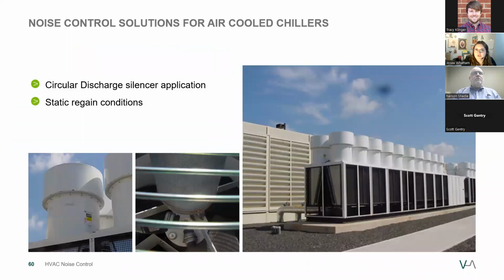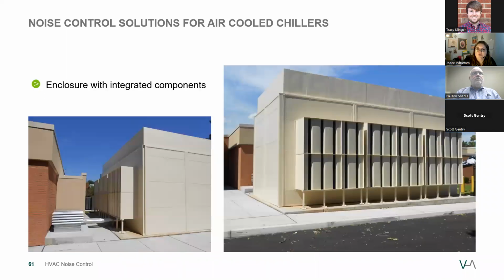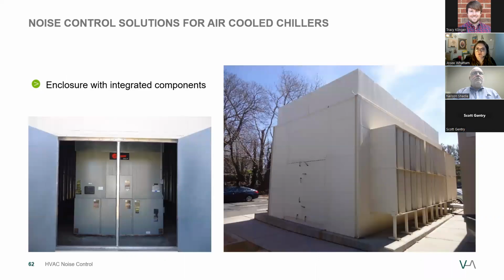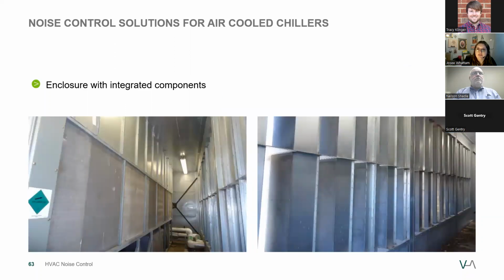This is another configuration, which includes circular discharge silencers. The center bullet of the silencer lines up with the fan hub diameter for static regain conditions. And another solution here is an enclosure with integral intake and discharge silencers. These photos are showing the end wall with double access doors. And the inside of the enclosure is tailored to the unit's dimensional allowances for maintenance and servicing.